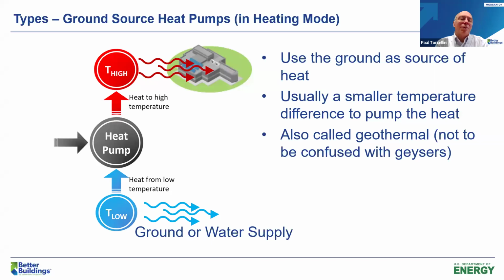So where we pull that heat from, whether it be outdoors, as shown in the last illustration, or from the ground, often the ground temperature is closer to the temperature that we want the heat. And so again, the less temperature difference we have to move, the less hard that heat pump has to work. So that temperature difference is really an important piece. Sometimes we have a ground supply, or if you're lucky enough, a water supply that's at a more advantageous temperature. It gives you a higher efficiency on that heat pump. Next slide.